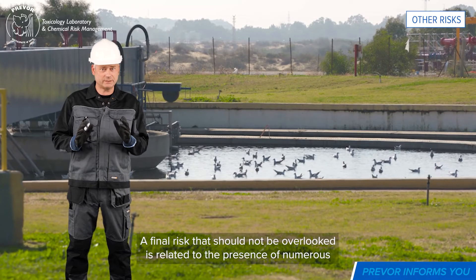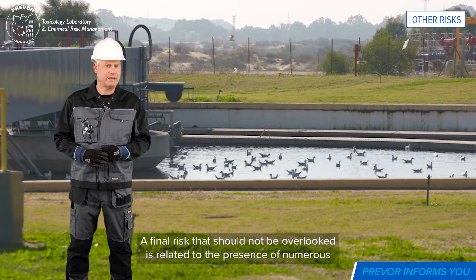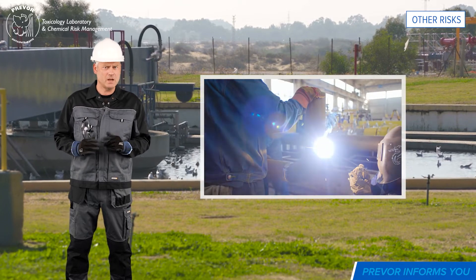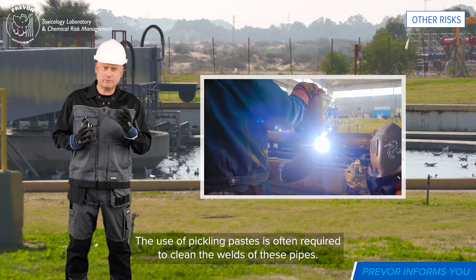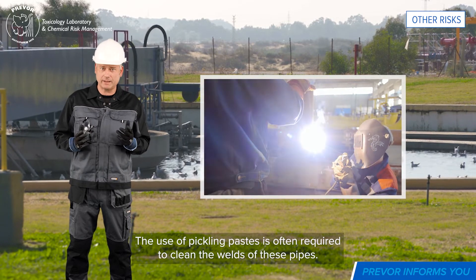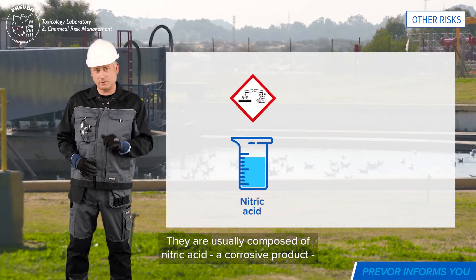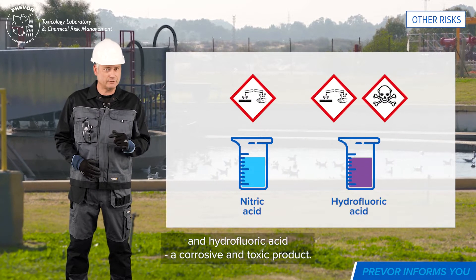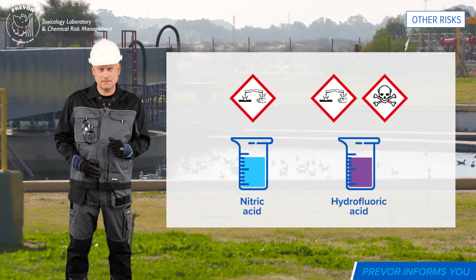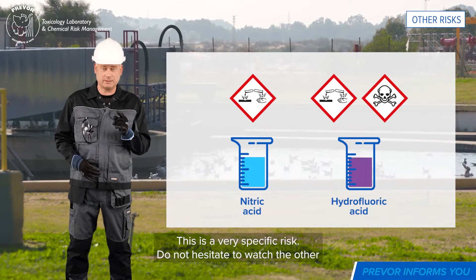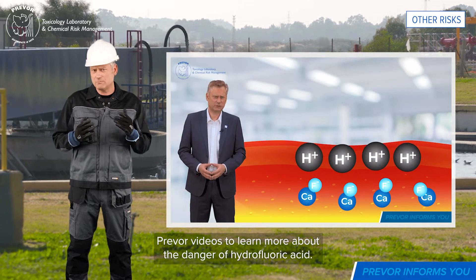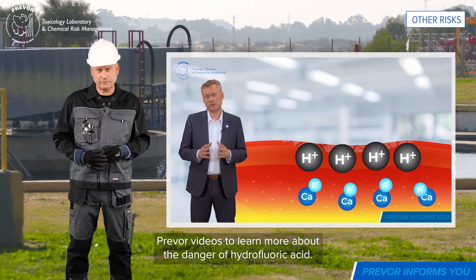A final risk that should not be overlooked is related to the presence of numerous stainless steel pipes in these facilities, which may require welding for maintenance. The use of pickling pastes is often required to clean the welds of these pipes. They are usually composed of nitric acid, a corrosive product, and hydrofluoric acid, a corrosive and toxic product. This is a very specific risk. Do not hesitate to watch the other PREVOR videos to learn more about the danger of hydrofluoric acid.